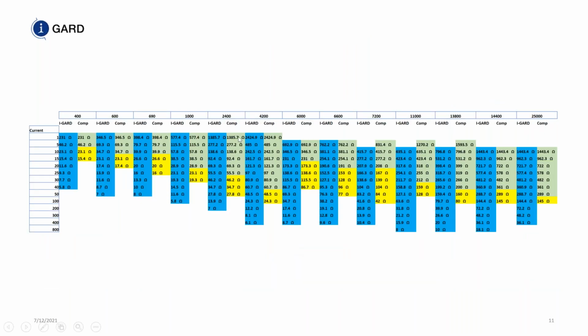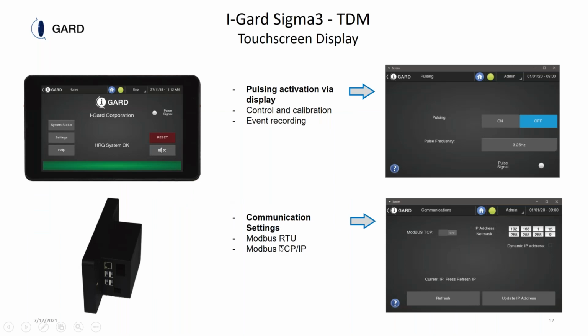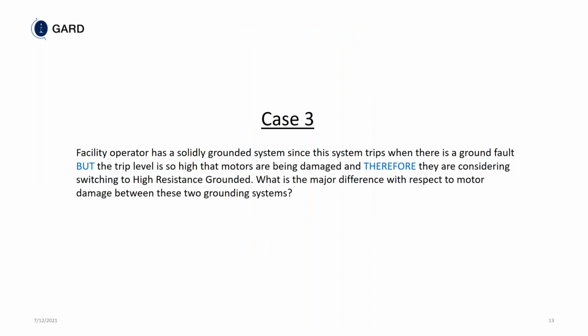Put both of them together, you have what our competitors can do, what they can't do, and what we can do. We also have, because you have to monitor both low and high resistance grounding systems for open and short circuit, we tell you whether there's an open or a short circuit with the Sigma 3, not like some of the competition who just says you have a resistor failure. There's communication, event recording, and calibration is necessary on site, because we have to calibrate the Sigma relay to your system, and your system is the one unknown in this.